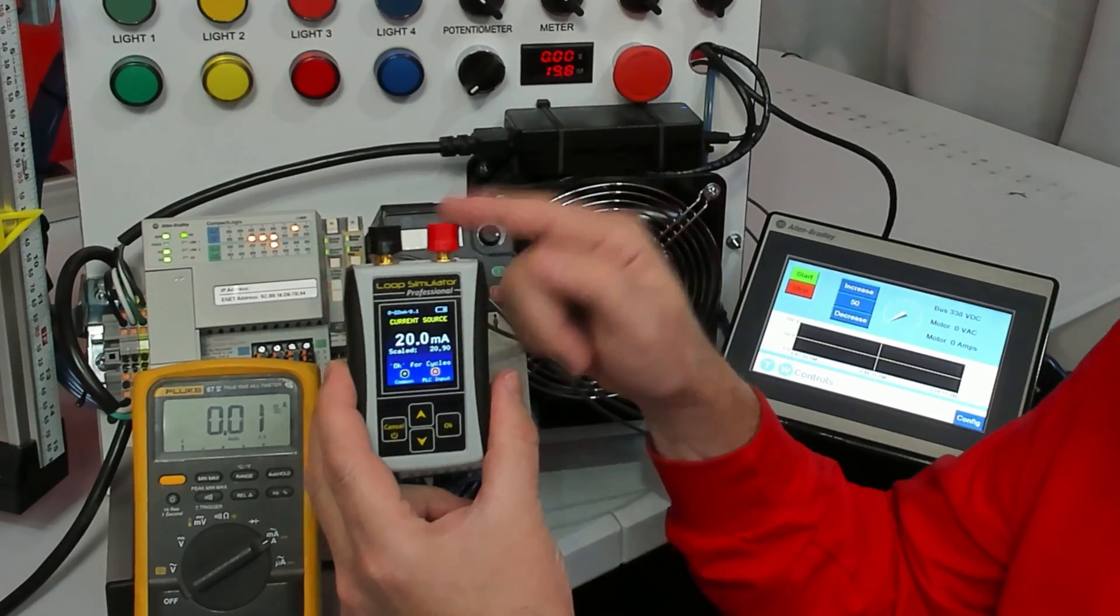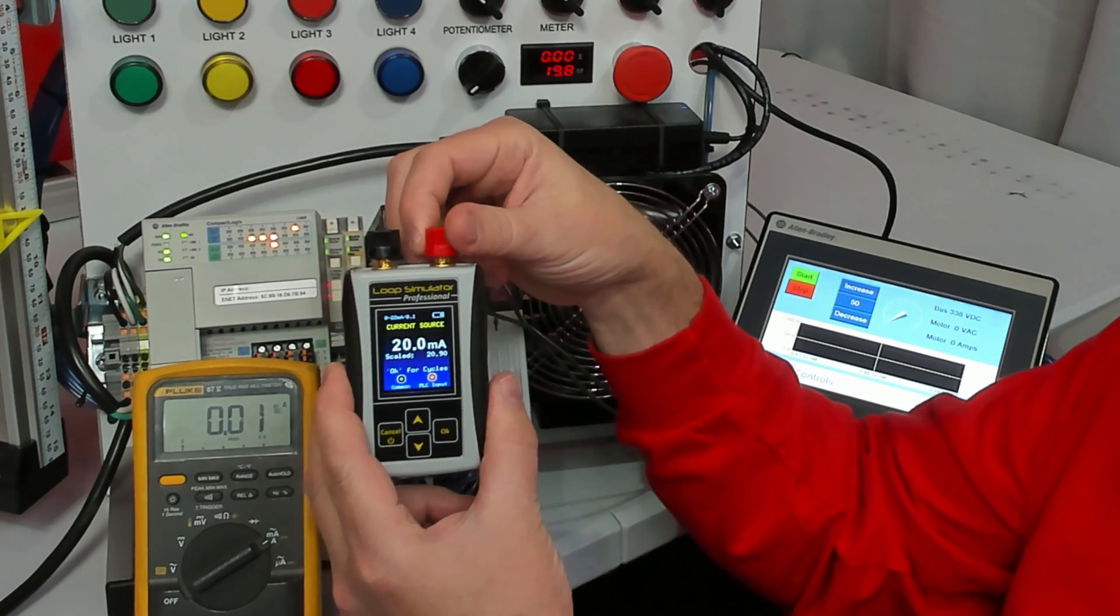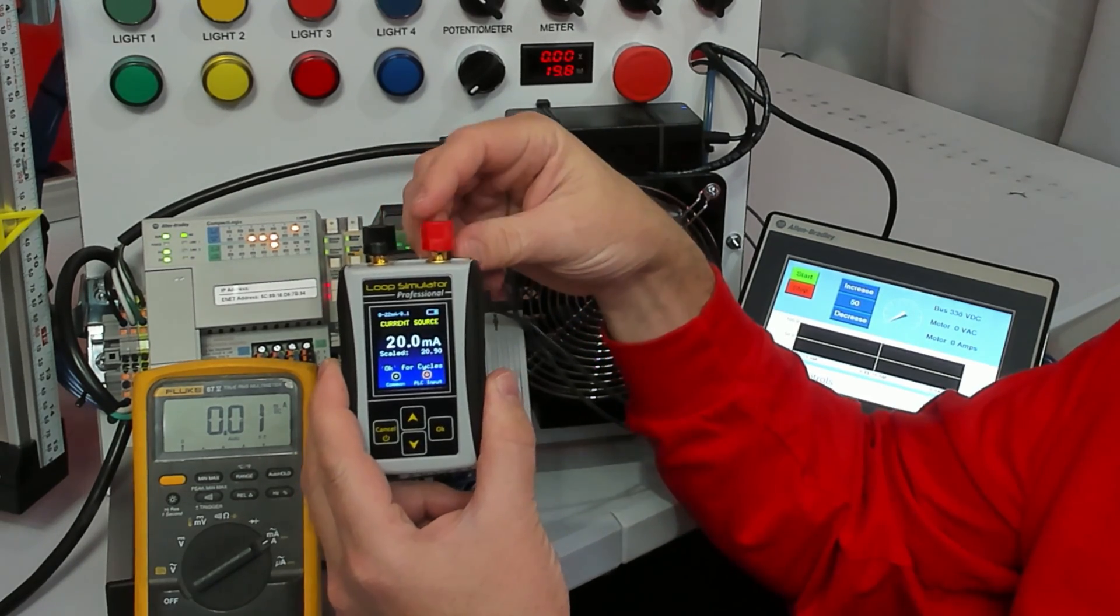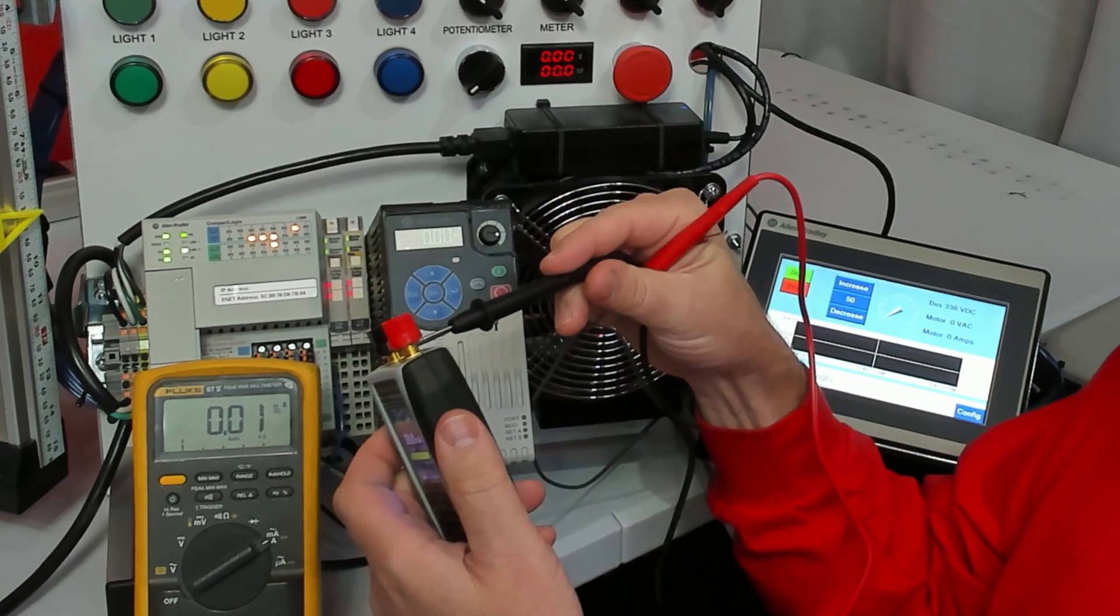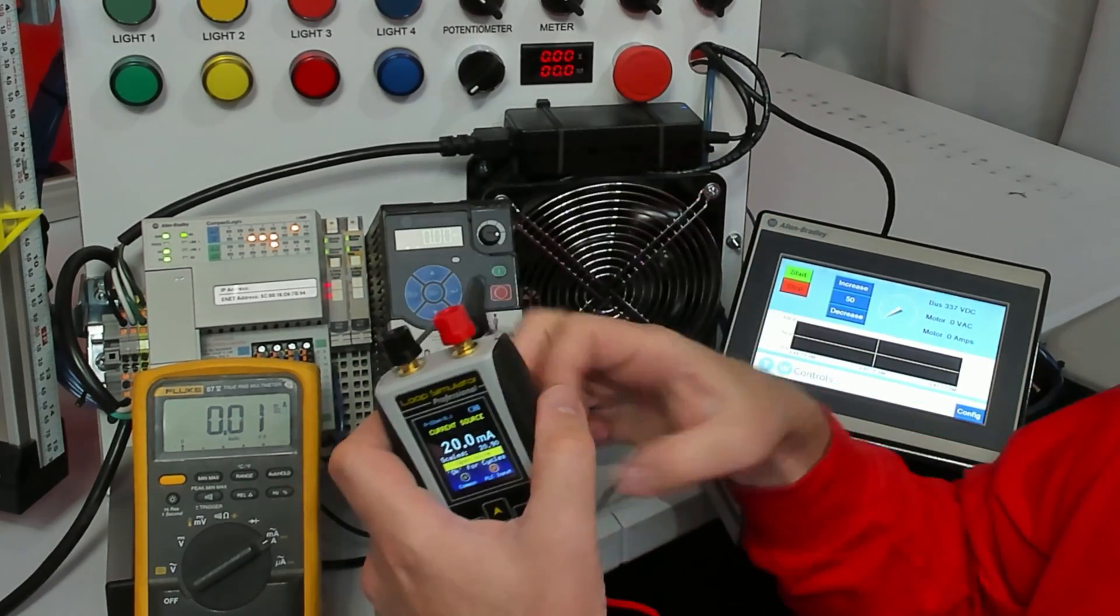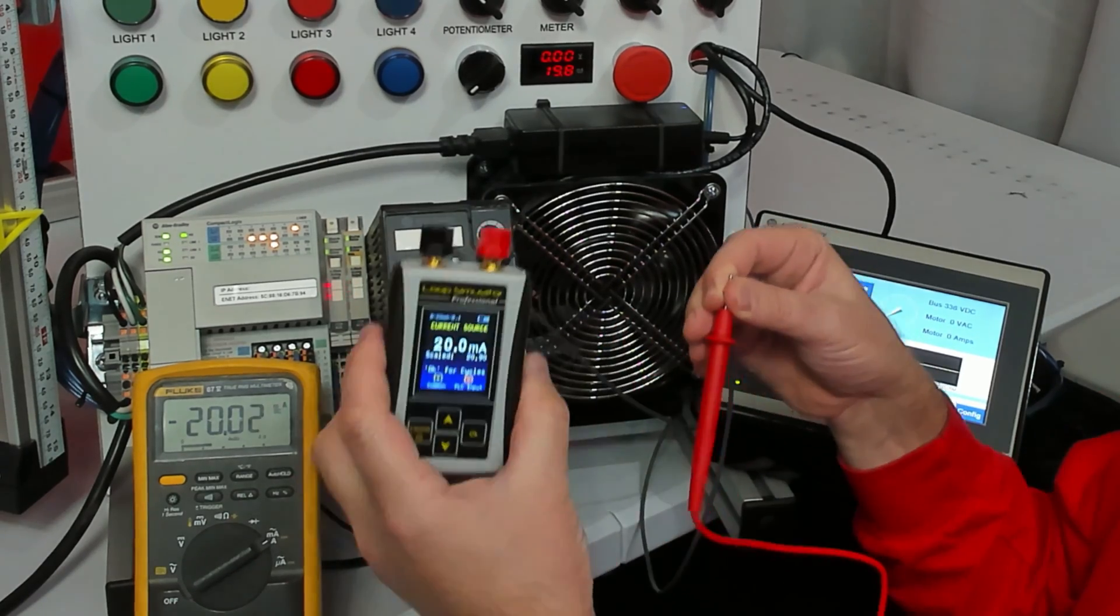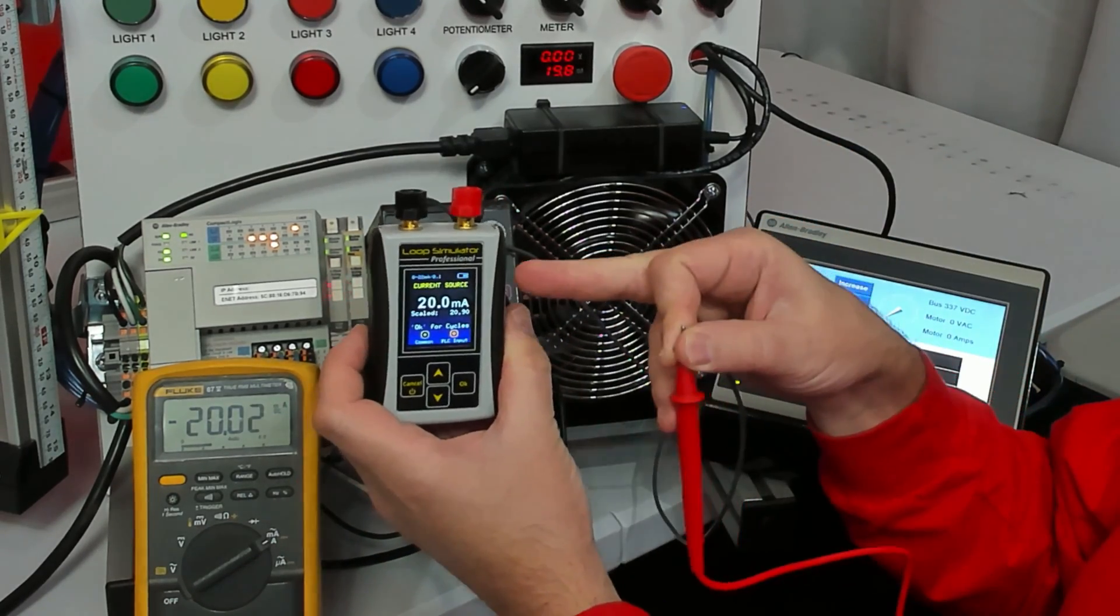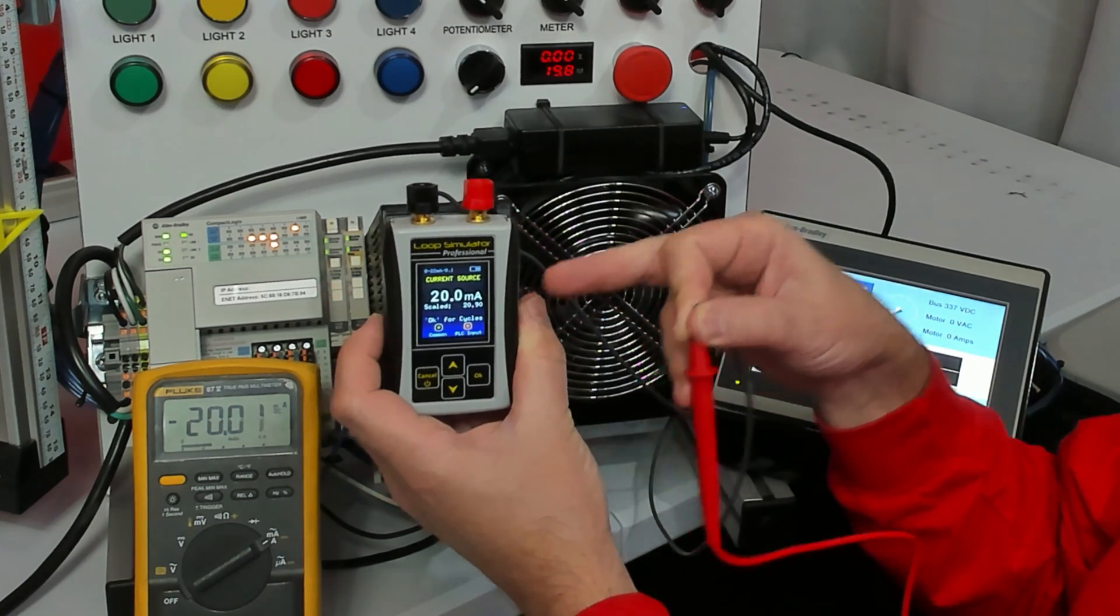The right way to measure milliamp signal is to break the loop and become part of it. So I'm going to just take one of the wires loose, it doesn't matter which one, and put the black lead in place of it and I put the red lead back on.